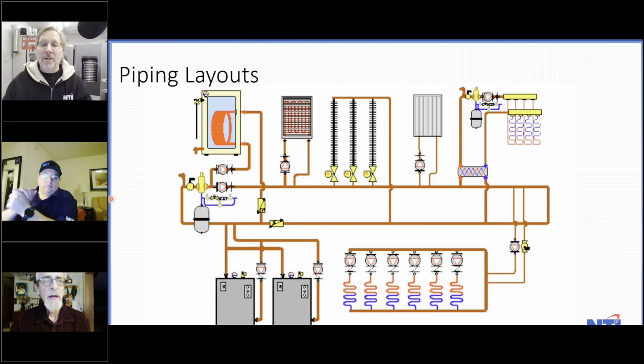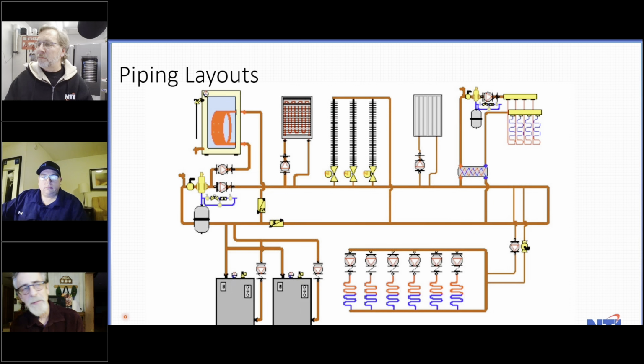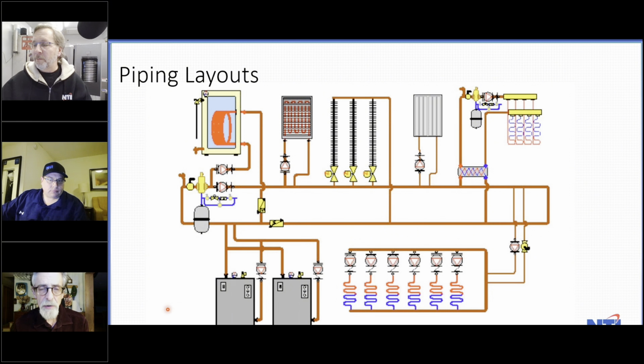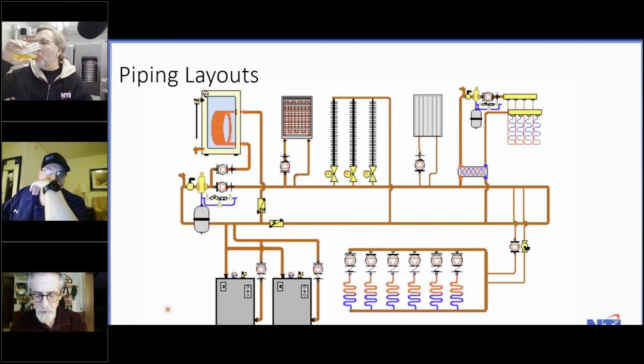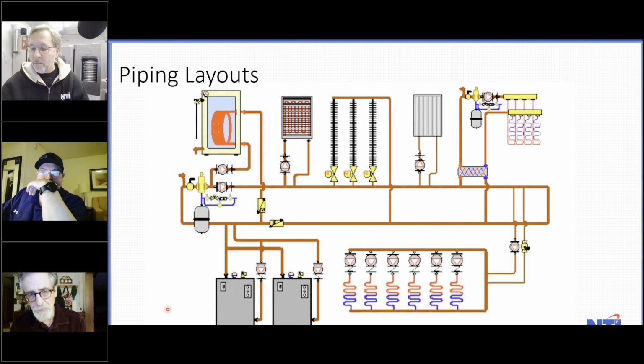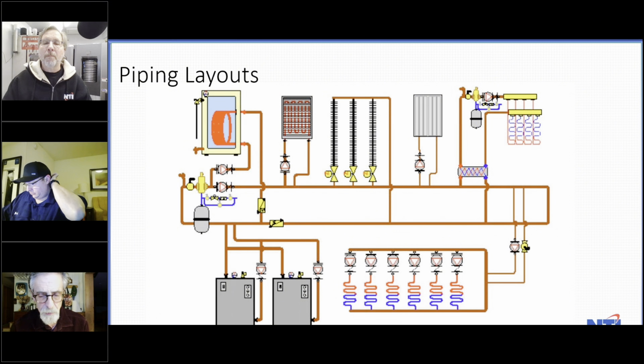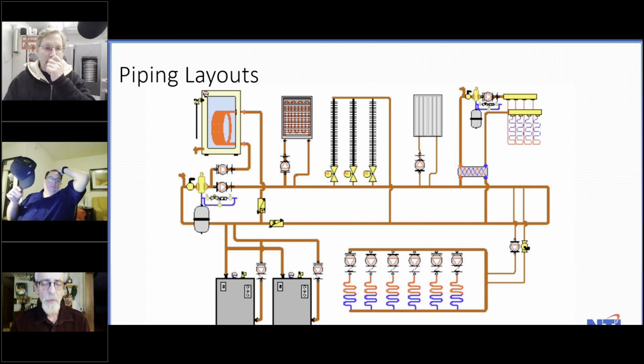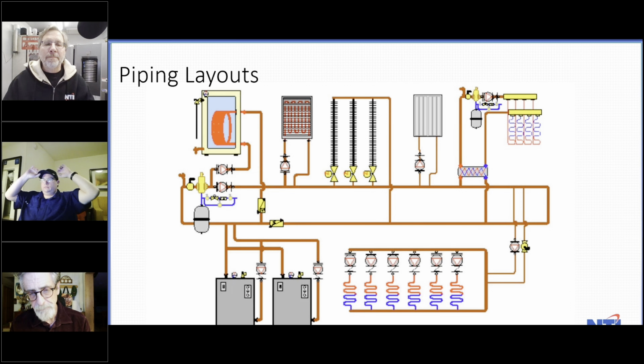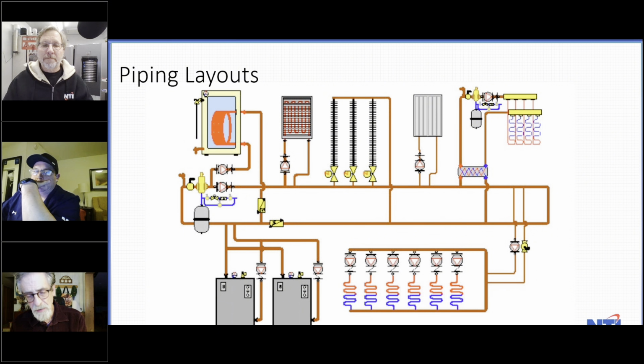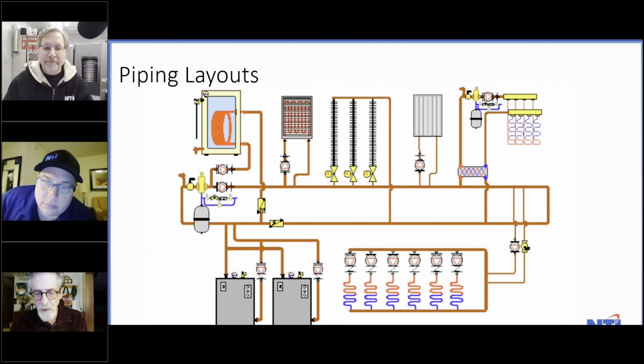Fascinating. So one thing I want to point out as well, we talked about earlier with glycol. Glycol and water will not mix naturally on their own. If you just pump glycol into a system without pre-mixing it, you could have a slug of glycol moving around that system for a year later. It's not going to naturally mix. So if you want to glycol a system, you want to pre-mix it and pump it in that way. Whether it's pumping it in or putting it in the Axiom pump, either way, it wants to be pre-mixed.